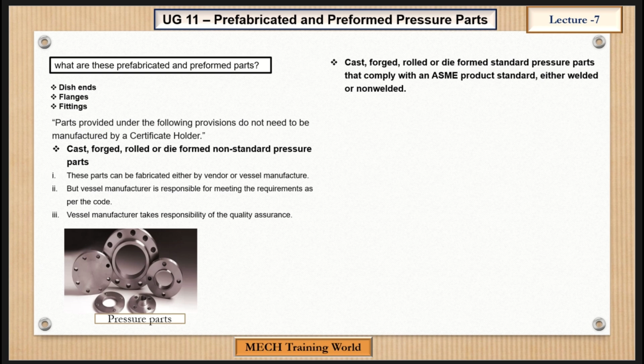And the next one is cast, forged, rolled, or die formed standard pressure parts that comply with an ASME product standard, either welded or non-welded. This clause says that parts that comply with an ASME standard do not need to be designed again. Some parts like flanges and pipe fittings are already manufactured based on pressure temperature ratings as per codes ASME B16.5 and ASME B16.47. So there is no need to design these types of components again. This is a time-wasting process, so that's why we directly buy from outside vendors. I hope you understand this second point.